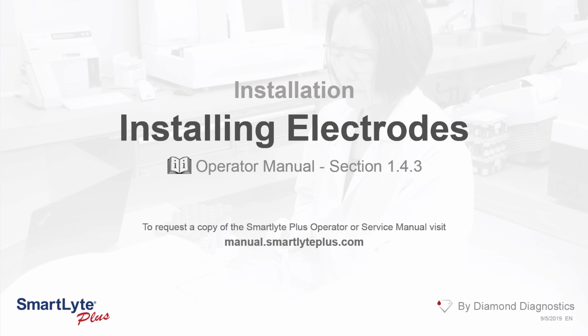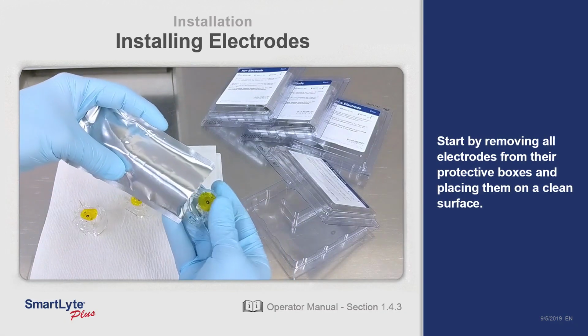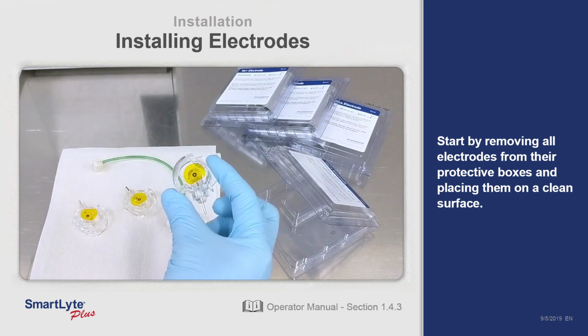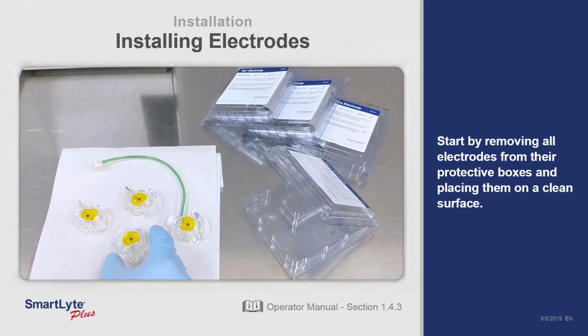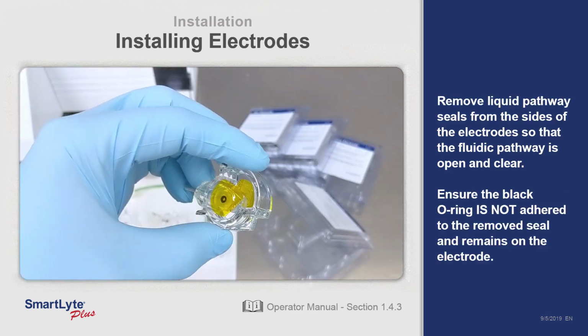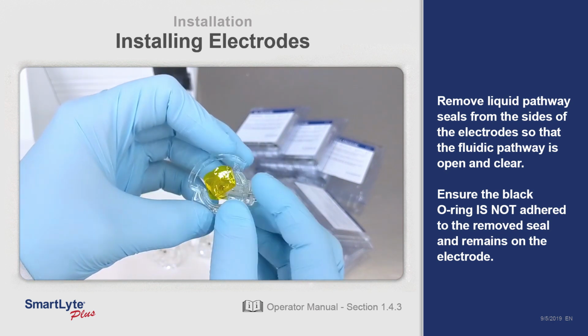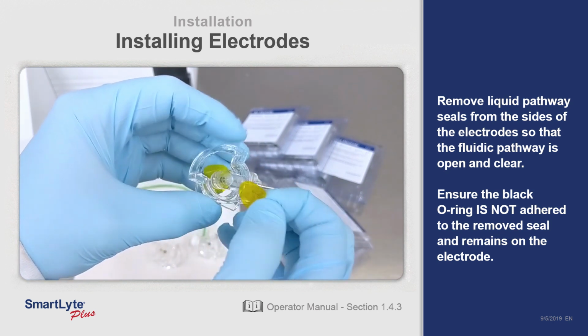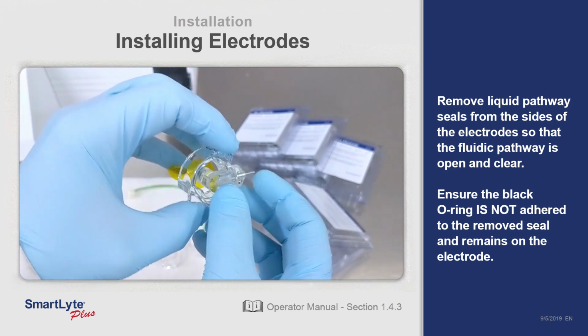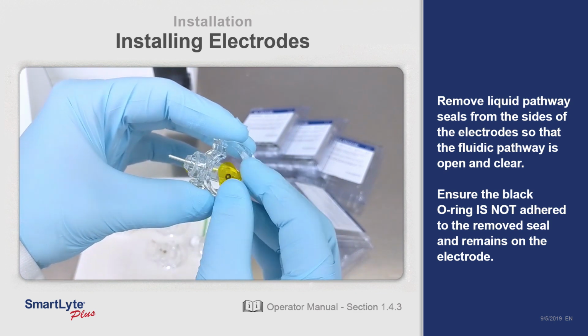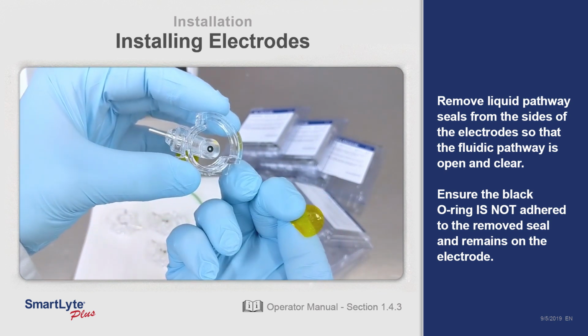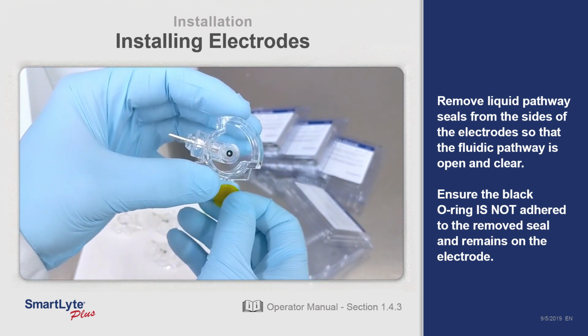Installing electrodes in the SmartLyte Plus. Start by removing all electrodes from their protective boxes and placing them on a clean surface. Remove liquid pathway seals from the sides of the electrodes so that the fluid pathway is open and clear. Ensure that the black O-ring is not adhered to the removed seal and remains on the electrode.